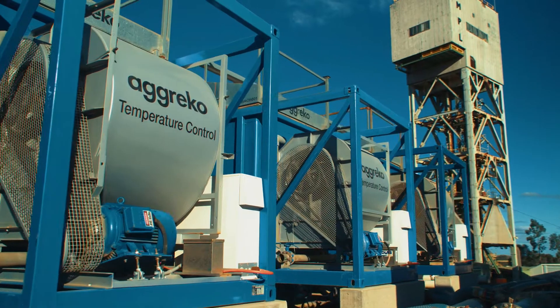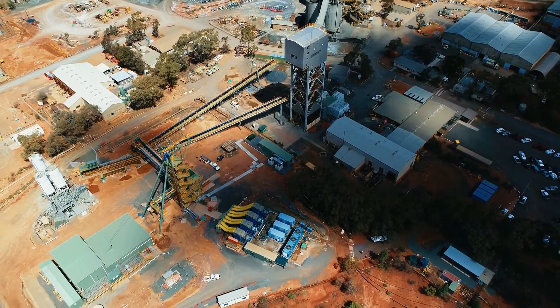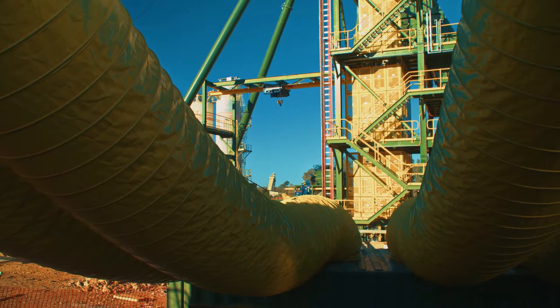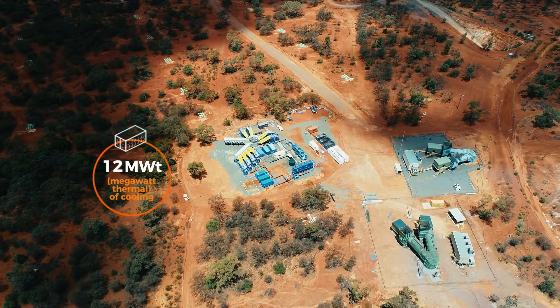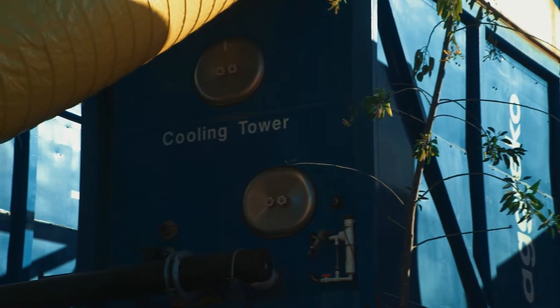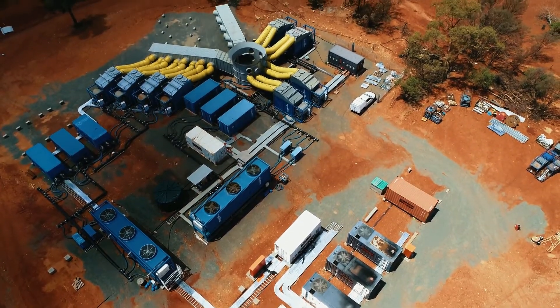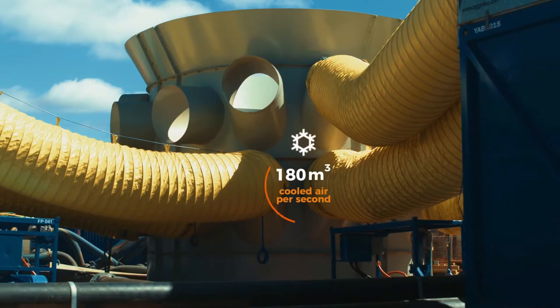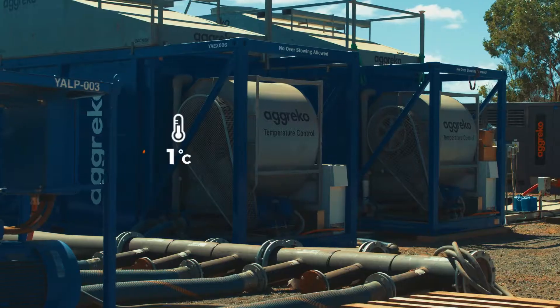And that's where Aggreko come in. As the leaders of underground mine cooling in Australia, our expert team were able to engineer a unique 12-megawatt thermal package utilising a range of specialised mine cooling equipment. From fluid chillers and cooling towers to diesel generators, we engineered a bespoke cooling solution that delivered 180 cubic metres of air per second into the mine at just 1 degree Celsius.